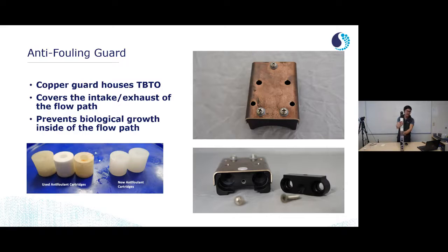And so right here, I have my anti-fouling guard. This is a copper guard that houses 2 cartridges of TBTO anti-fouling chemicals. These are the exact same things we used in the SBE37s, SBE16s, SBE19s, etc. And they prevent biological growth inside of the flow path. And so what happens is you have one cartridge that's covering up the intake of the flow path and one cartridge that's covering up the exhaust of the flow path. And so this flow path, as we saw before, shaped like a U, any water that's inside of here is being exposed to TBTO chemicals, preventing any biological growth from coating your oxygen sensor, your conductivity cell, your pH sensor, etc. This is really going to extend the deployment lifetime of your instrument significantly.